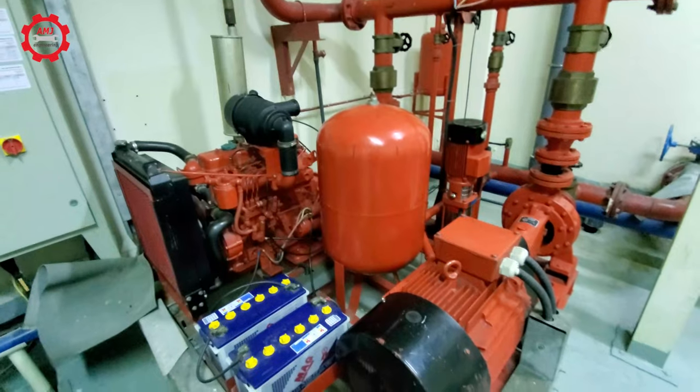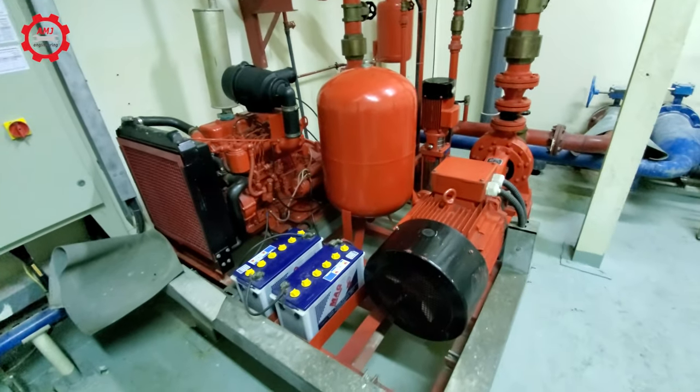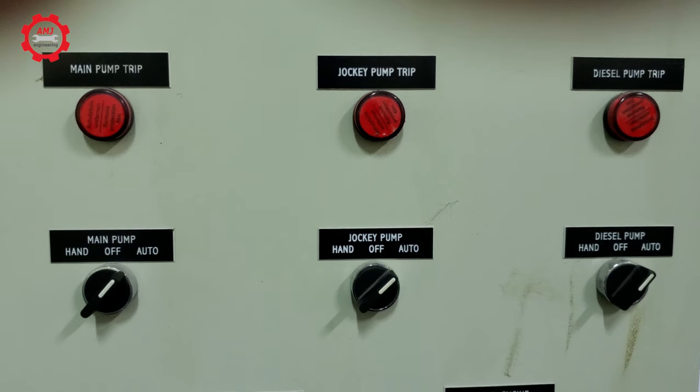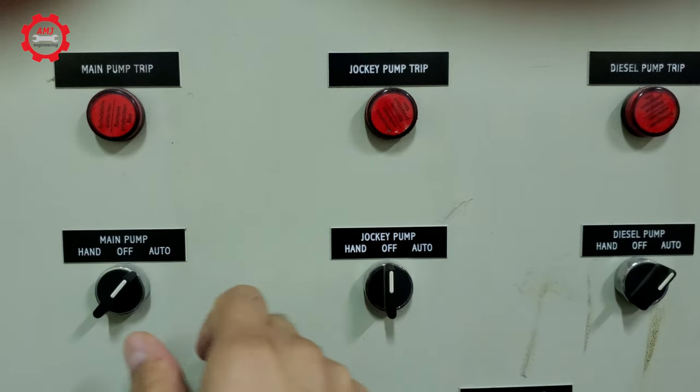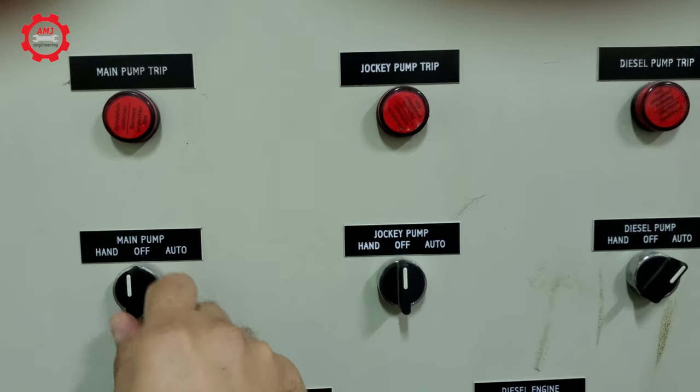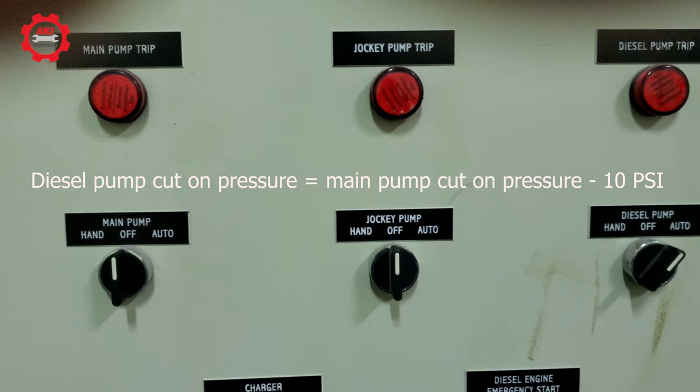In order to test the diesel pump, the same step should be performed. The jockey and the main pump controllers both should be placed on off position. Note that the diesel pump should start automatically at 10 psi less than the main pump cut on pressure, and it should be stopped manually.